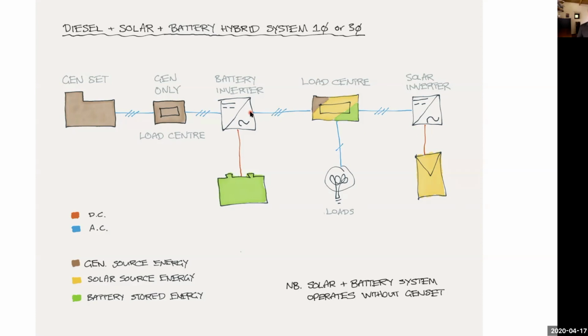To my mistake, I tried this once without thinking about it, and the smoke did in fact come out of the inverter. So you've got to make sure the inverter is designed for reverse power flow and is able to charge batteries with that. So in this diagram, we've got an inverter that is bidirectional on its load port. Energy can flow from the solar inverter to the battery inverter and charge the battery. So that's called AC coupling.